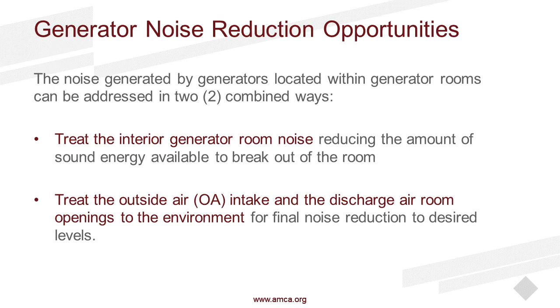There may not be enough footprint or real estate within the building to put rectangular silencers downstream of the radiator or the outside air intake, so you may have to use acoustic louvers. Those are made in 4-inch thicknesses up to 2-foot depth. You may also want to absorb sound within the room itself to dull it down, like we did with the equipment yard.